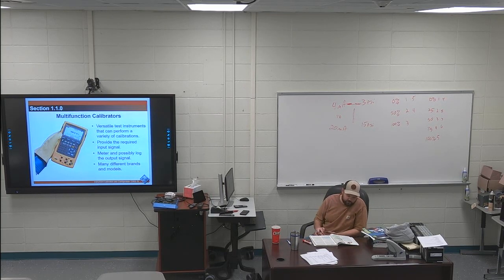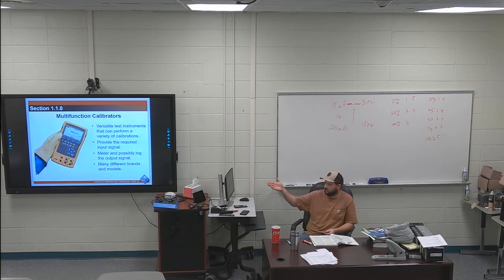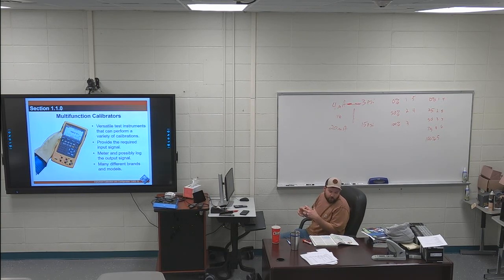111, input signals or energies. First sentence is highlighted. Instruments that are in direct contact with the process are designed and manufactured to operate within a specified process input energy range. So that's like the lab equipment out there. A control valve is made to operate within 3 to 15 psi or something like that, or a valve is made to operate up to 100 psi. Everything has a range it can operate in, and if you go outside that range, it's not going to be a calibrated setting. It's kind of an unknown because it was never calibrated at that level, and it can also damage the equipment.